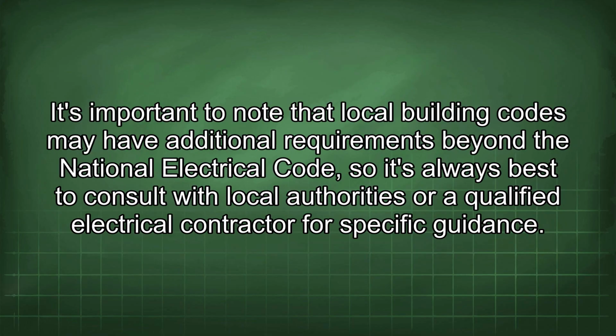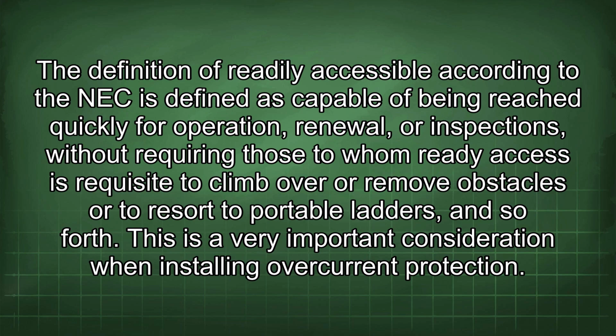It's important to note that local building codes may have additional requirements beyond the National Electrical Code, so it's always best to consult with local authorities or a qualified electrical contractor for specific guidance. The definition of readily accessible according to the NEC is: capable of being reached quickly for operation, renewal, or inspections, without requiring those to whom ready access is requisite to climb over or remove obstacles or to resort to portable ladders, and so forth. This is a very important consideration when installing overcurrent protection.